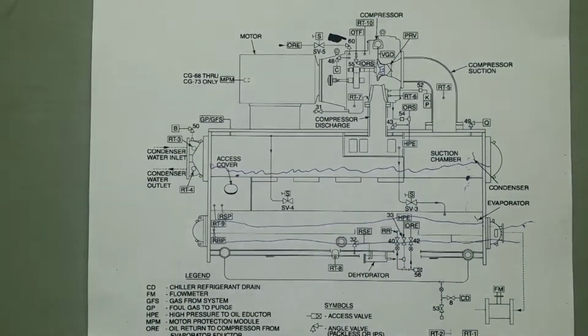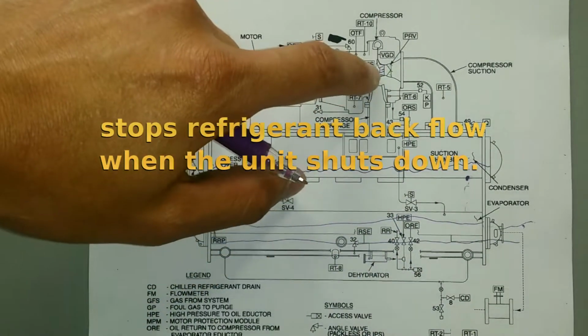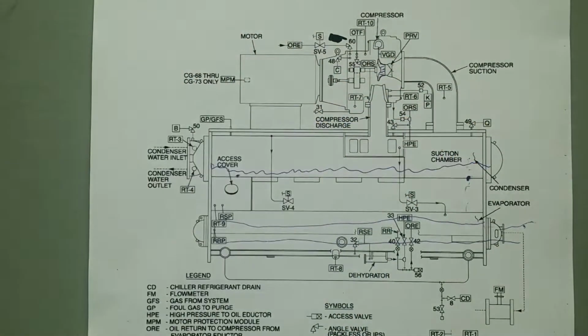Also, when the system gets shut off, those valves close completely, and when they are completely closed, there cannot be any backflow of the refrigerant that is over here at high pressure back into this side.